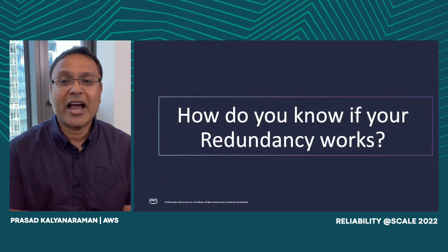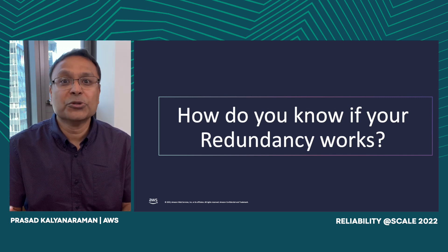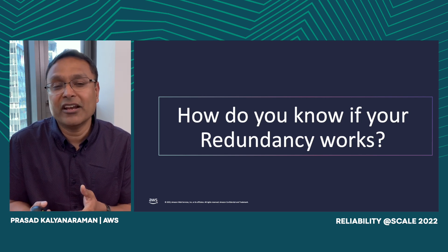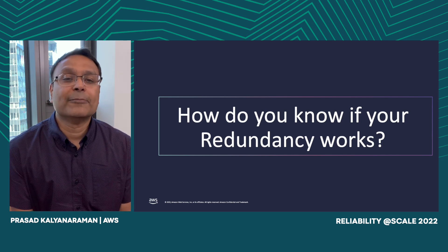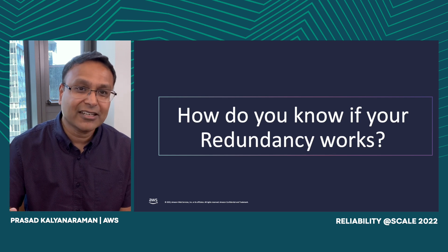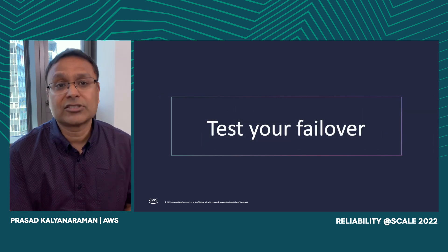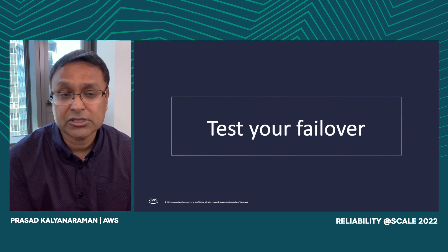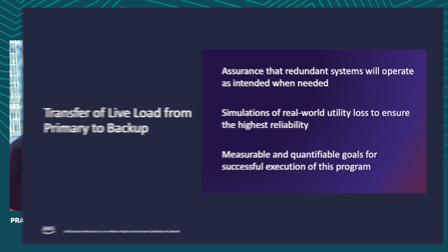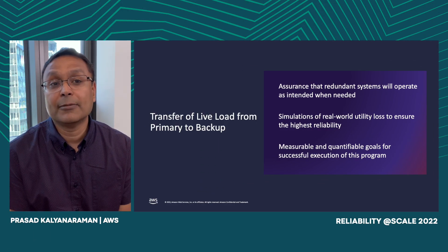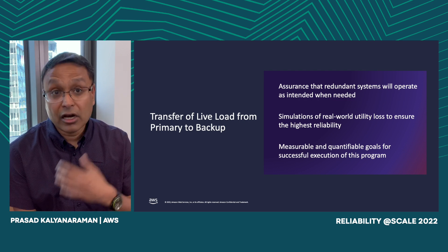How do you know your redundancy works? As a software leader, you know you should never rely on failover only when you need it — because when you need it, it may not work. Generally you build active-active systems, but that's not always easy with physical infrastructure. So we test failover pretty frequently for both our electrical setup and our mechanical and cooling systems, including control systems. We induce real-world failures like generator failures, breaker trips, and utility failures fairly frequently, measuring all of it. We have quantifiable goals for how many times we do primary-to-backup failovers, and we learn from each one.